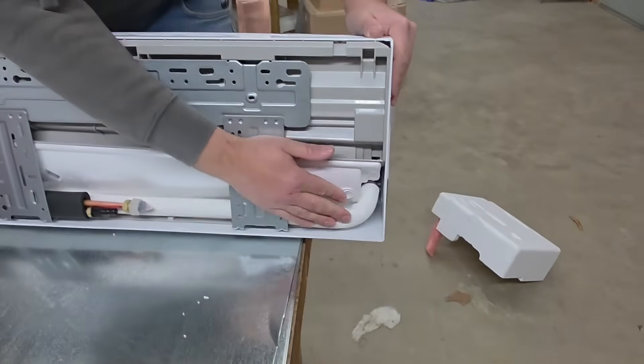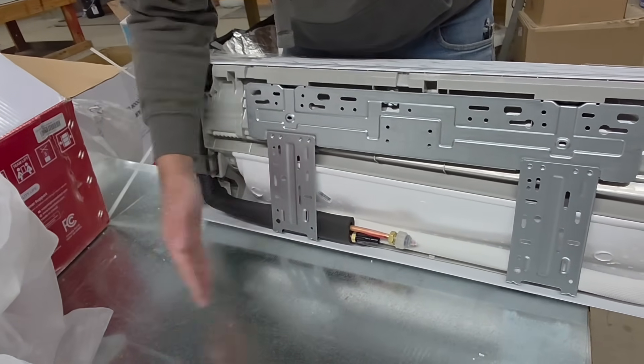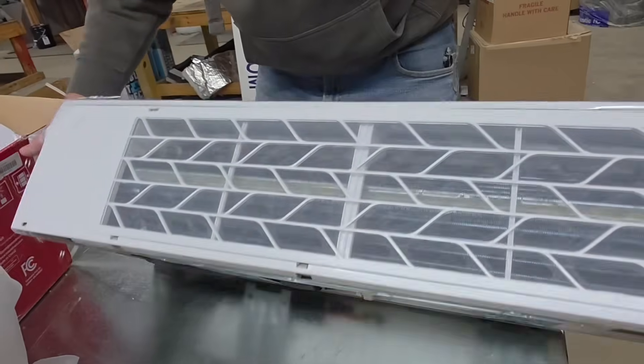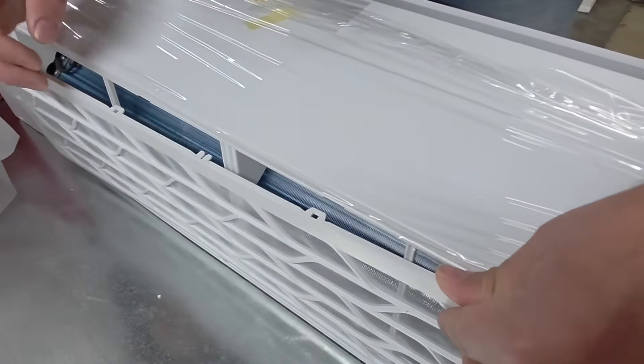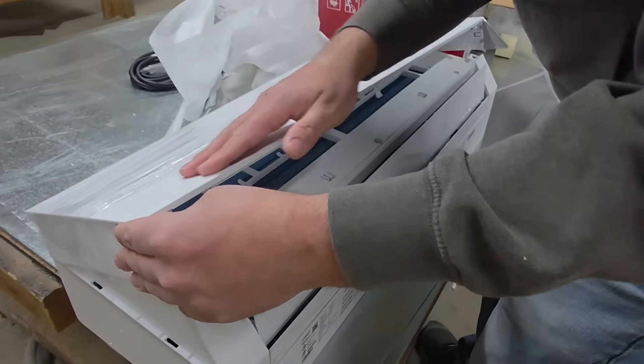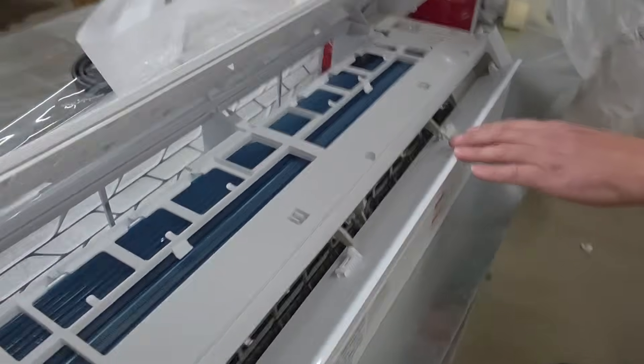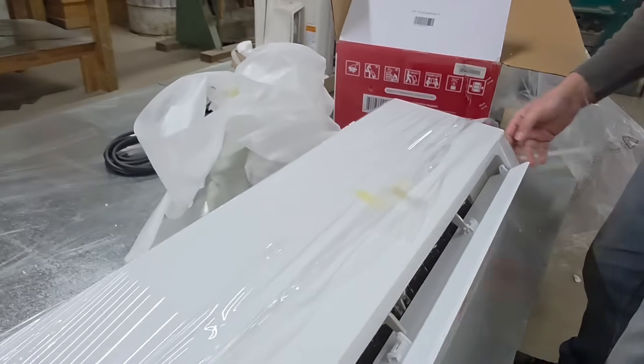I love it when the filter's on top. Looks like we got our cable and a screw that holds the bracket on. Drains on this side — we'll probably want to move that over. Not a lot of line set here but there's enough; looks like at least a foot. The coil is coated just like the outdoor unit. Looks like a good looking indoor unit.